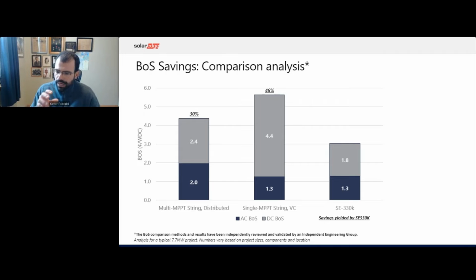The SE330k DC optimized solution provides the lower balance of system costs, as you can see here, for both AC and DC circuits. The reasons for this advantage are the use of DC optimization, which reduces the number of string count and therefore DC balance of system. The virtual central configuration reduces AC balance of system, and the size of the inverter, which is 330 kW, reduces the number of inverters per plant. As you can see, the savings are between 30% to 46% between the two string inverter solutions and the SE330k system. Okay, so that's what I'm showing here: AC balance of system in blue, DC balance of system in gray, and then the number on the top, that's the savings in percentage between the other solutions and our solution.